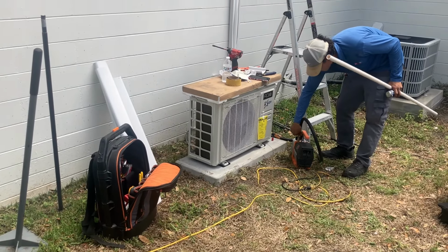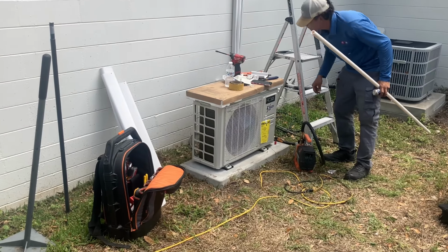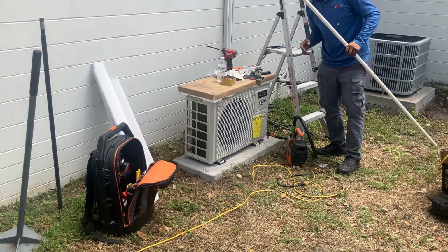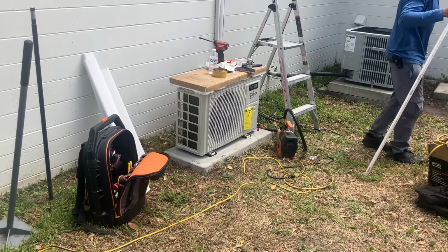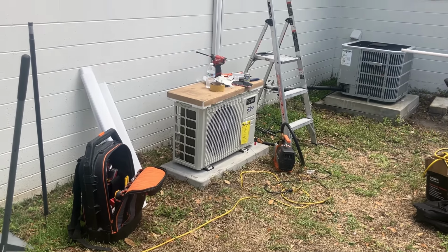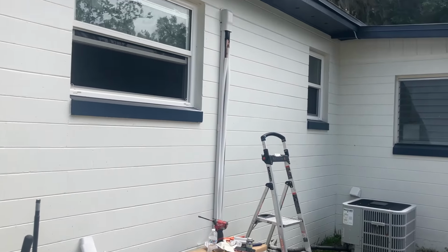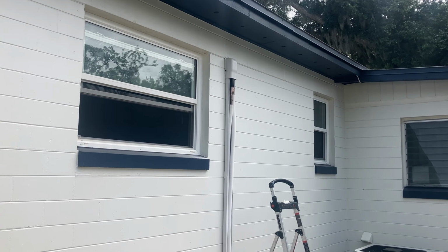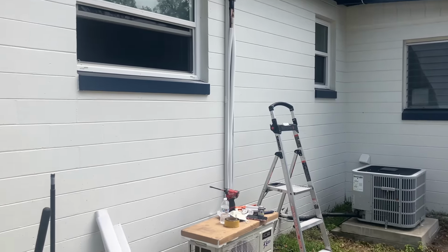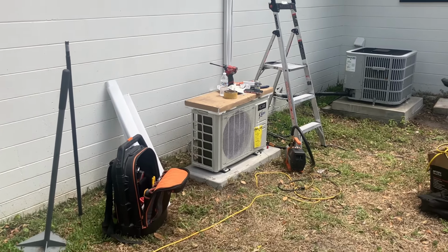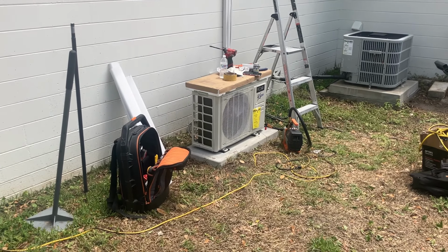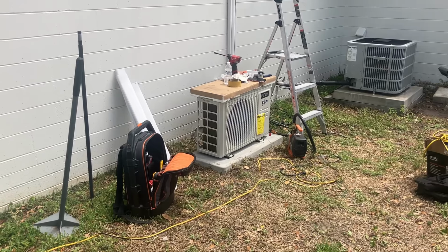Remember, if there's going to be a leak, it's going to be there and be present now, and leaks don't fix themselves. You skip this step, you're setting up the system for failure, and we don't want to have that. We want to make sure the only maintenance this homeowner needs to worry about is cleaning that filter on the indoor unit and making sure that outdoor coil is clean at all times.